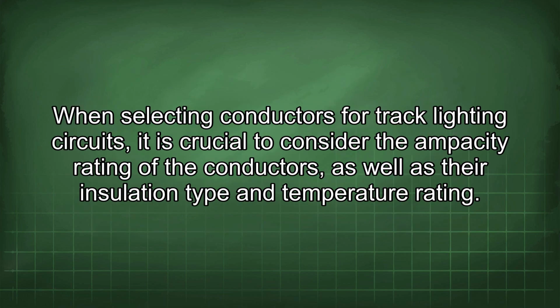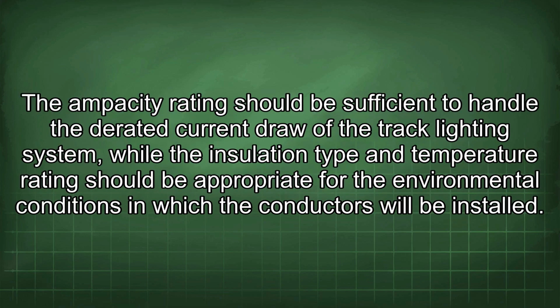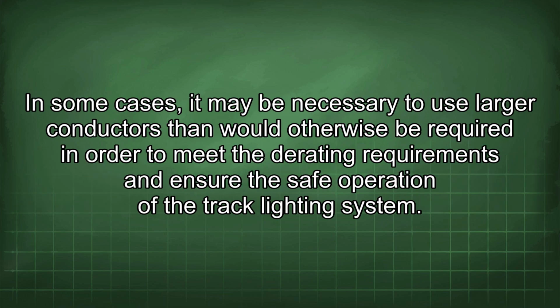When selecting conductors for track lighting circuits, it is crucial to consider the ampacity rating of the conductors, as well as their insulation type and temperature rating. The ampacity rating should be sufficient to handle the derated current draw of the track lighting system, while the insulation type and temperature rating should be appropriate for the environmental conditions in which the conductors will be installed. In some cases, it may be necessary to use larger conductors than would otherwise be required in order to meet the derating requirements and ensure the safe operation of the track lighting system.